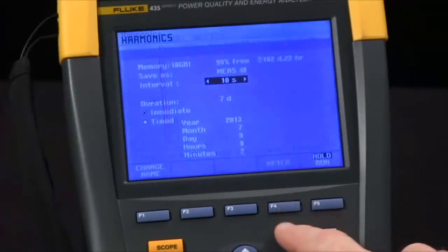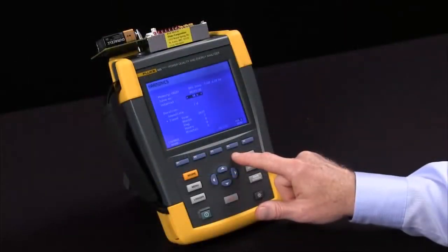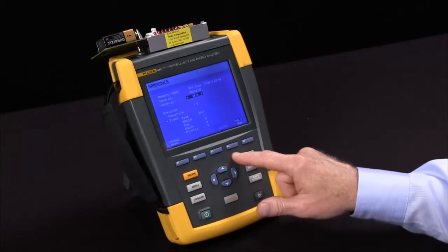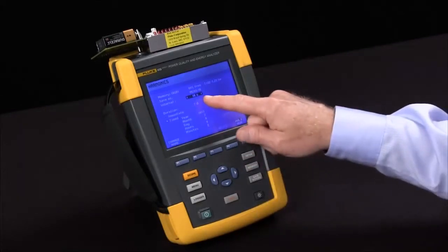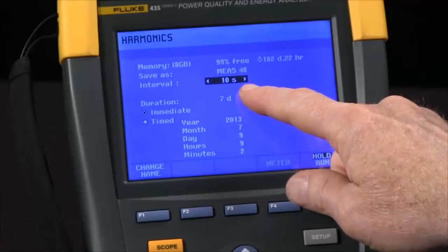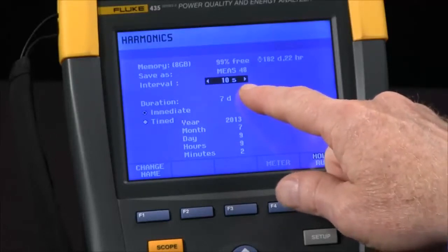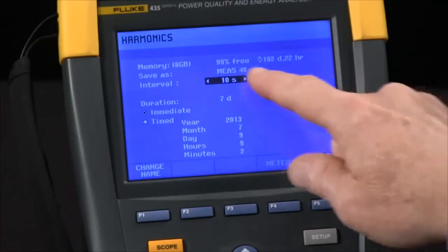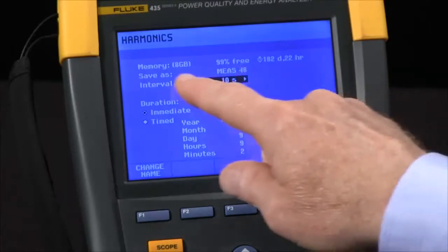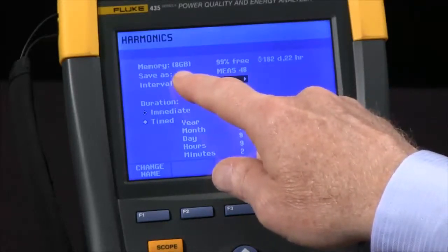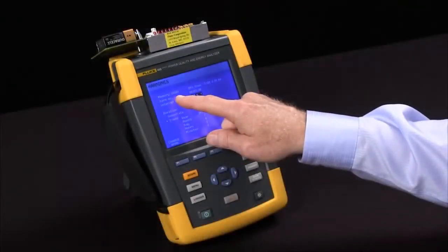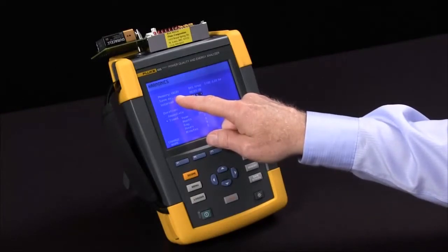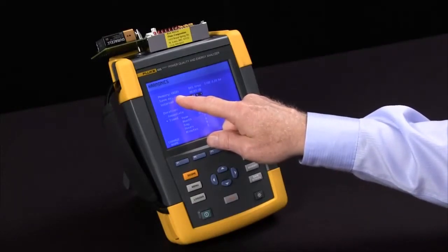The timed test option is very helpful for determining file size when doing trending. Right now, with the default 10-second interval, we could record for 182 days, but that would create an 8-gigabyte file — much too large to deal with effectively using PowerLog software.